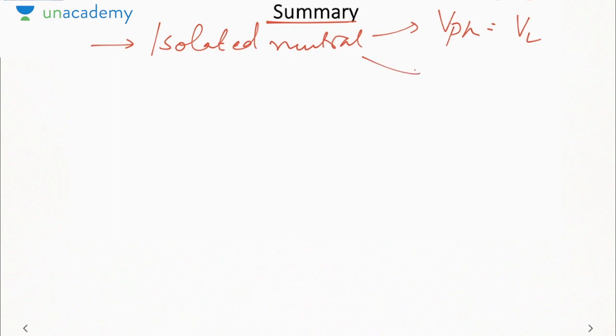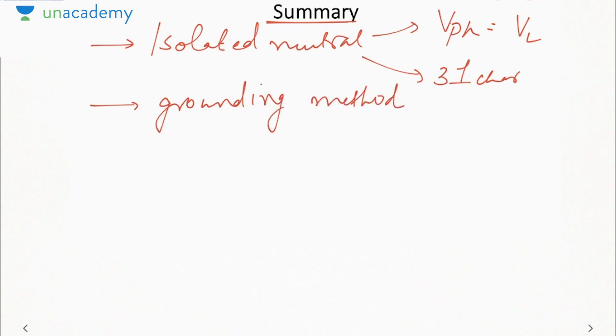So let us summarize what we covered in this lecture. We first saw the case of isolated neutral, and we saw two disadvantages. One was phase voltage became equal to line, and one was the 3 times line charging current flowing through the grounded phase. Then we saw the grounding method, which was system grounding and equipment grounding. System grounding was also called as neutral grounding. We were grounding the neutral to avoid high voltages. And in equipment grounding, we were grounding the outer body to provide a low resistance path to the flow of stored charges. Then we saw the methods of neutral grounding.